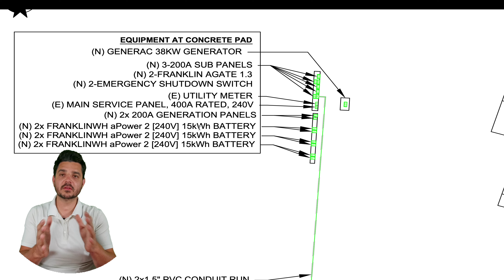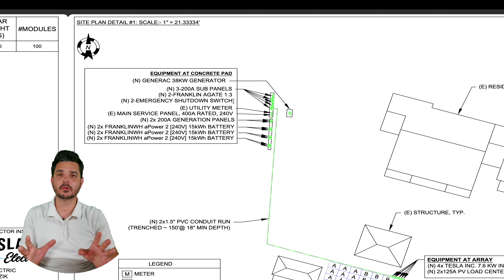We have 2 emergency shutdown switches. Basically, when first responders come out to site, if they turn those knobs, the whole system, batteries are shut down, the backup is disabled, it won't turn on the generator, the solar inverter shuts down. It basically kills the site for emergency power. So all the solar equipment goes down, and then they can just shut off the electrical equipment like they normally would for any traditional site.